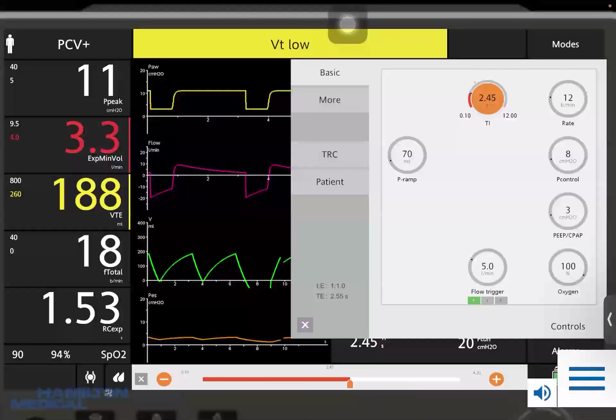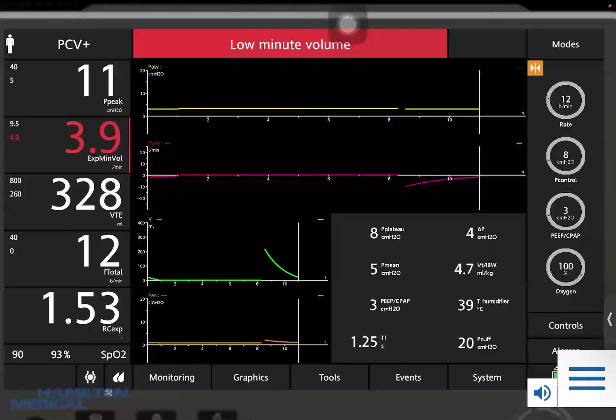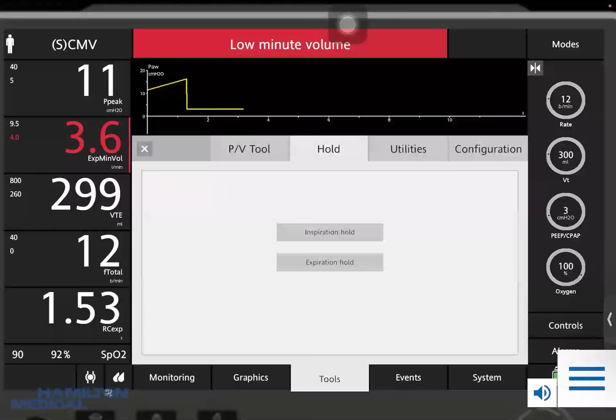So here, how do we check whether there's auto PEEP? You have to check with an expiratory hold. We'll make it volume control ventilation. So you do the expiratory hold and check the total PEEP. This is the total PEEP, which is 3.6, and this is the extrinsic PEEP we have applied. So the auto PEEP is total PEEP minus extrinsic PEEP, which is around 0.6. That is acceptable. We should keep the auto PEEP less than 5.